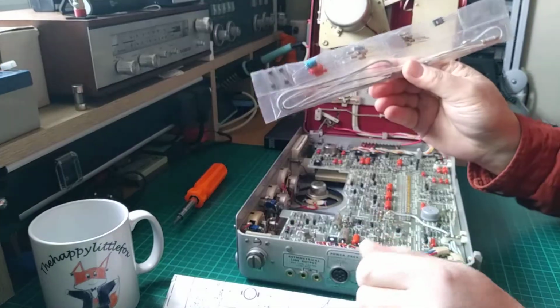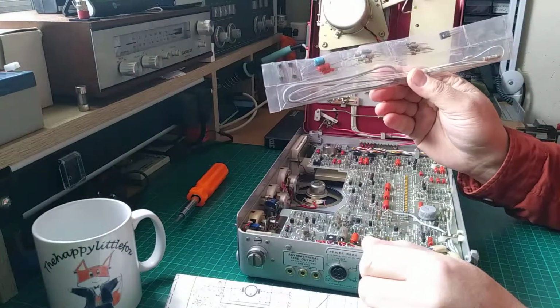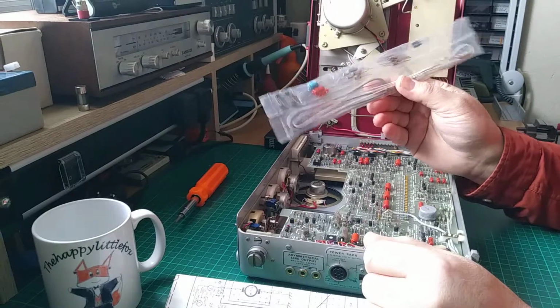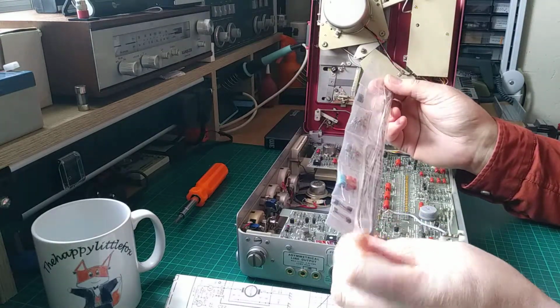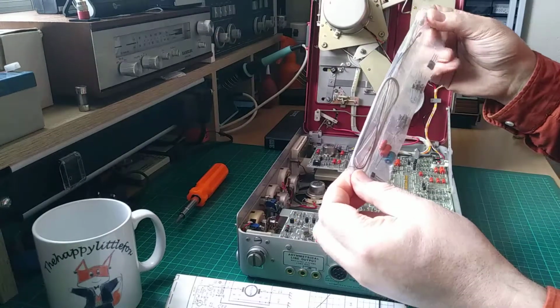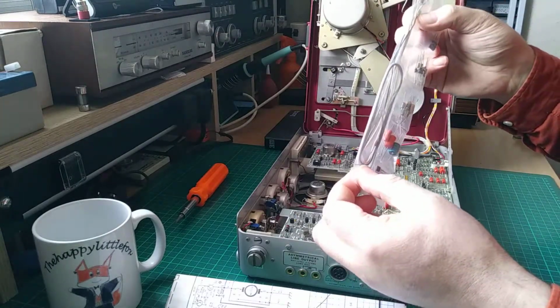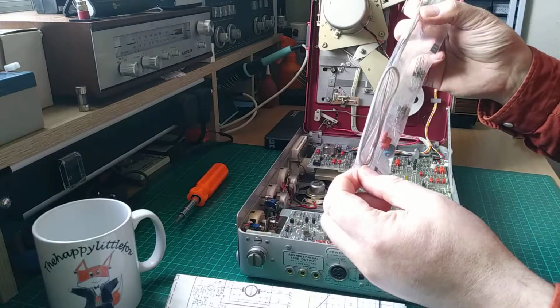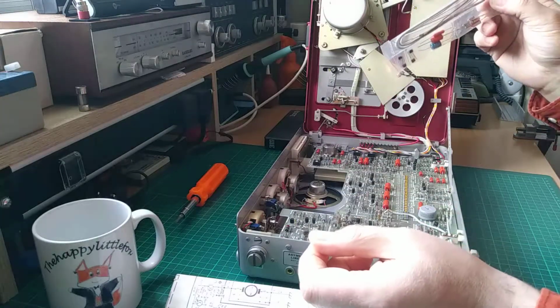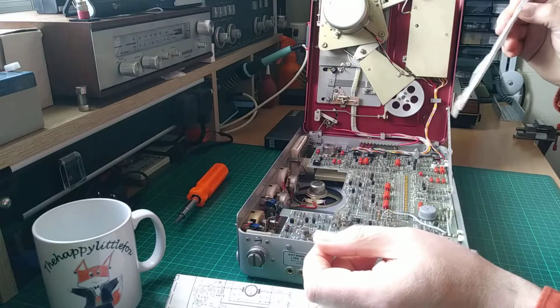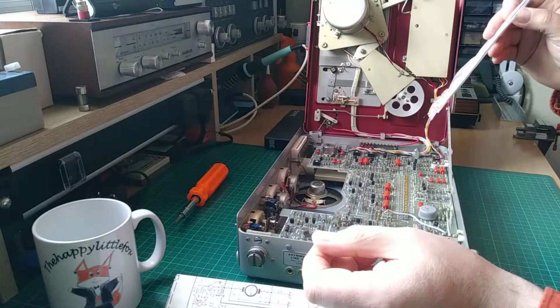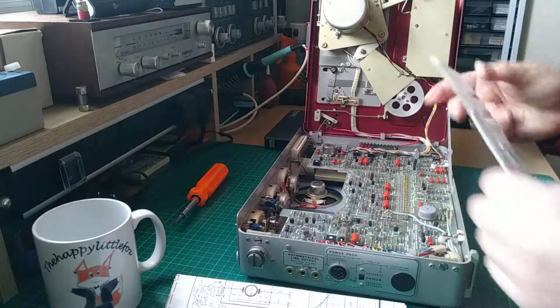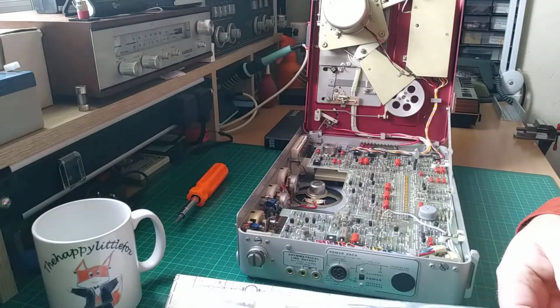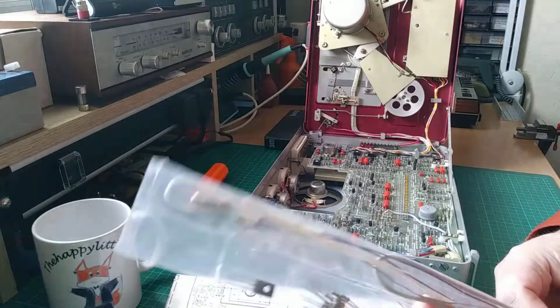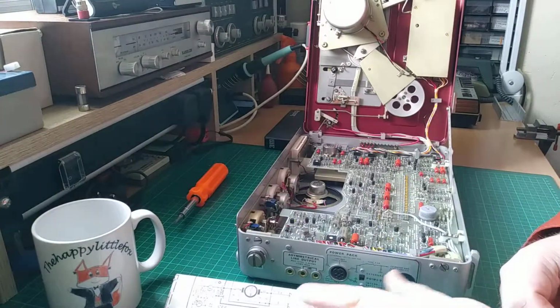And what else do we have here? We have a set of spare components for repairs in the field. And not only that, you're perhaps wondering what this long piece of wire is in here, and the connection that is on there, as well as a little probe. There's a facility on here for you to plug that into. I can't actually remember where it is, but there's a little test point somewhere. And then that actually turns the VU meter into a voltmeter. So you can do some voltage checks and service this machine in the field, as it were.